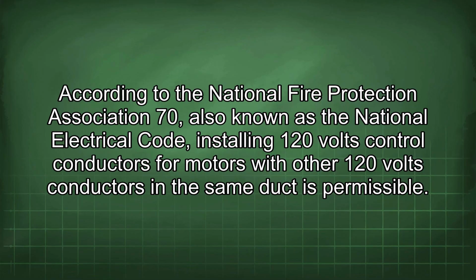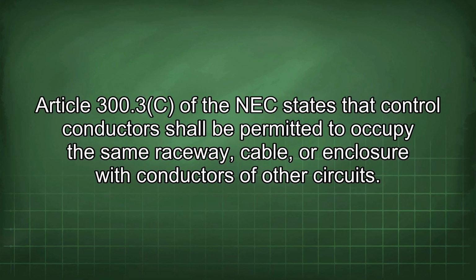According to the National Fire Protection Association 70, also known as the National Electrical Code, installing 120 volts control conductors for motors with other 120 volts conductors in the same duct is permissible. Article 300.3c of the NEC states that control conductors shall be permitted to occupy the same raceway, cable, or enclosure with conductors of other circuits.